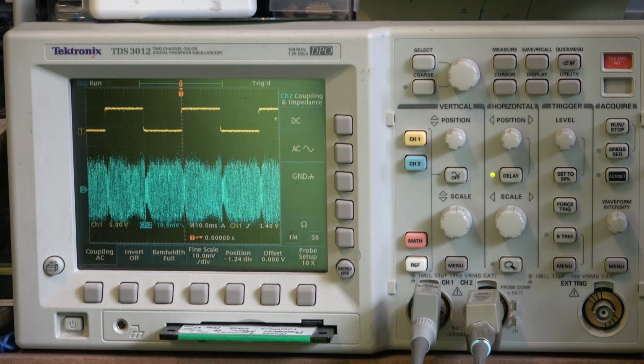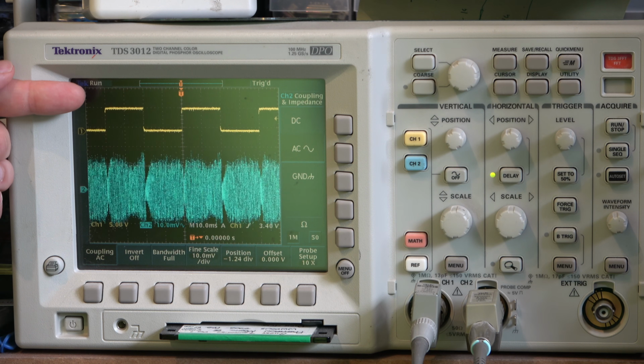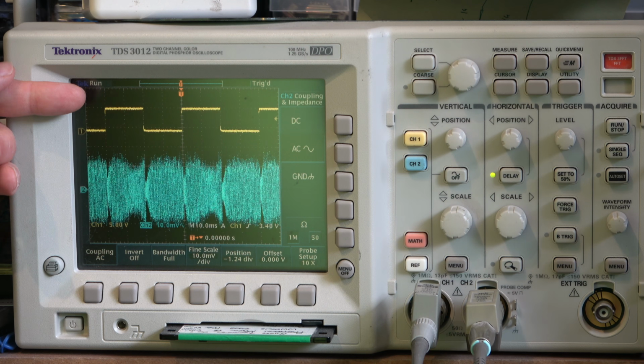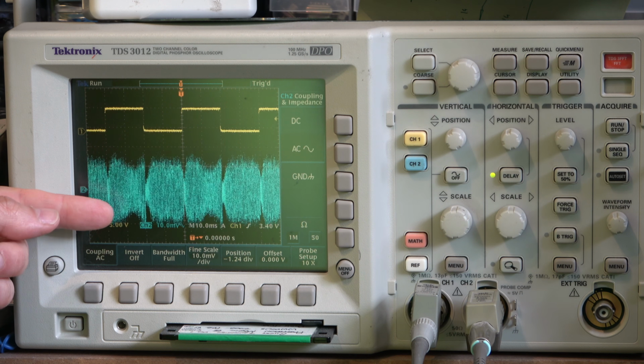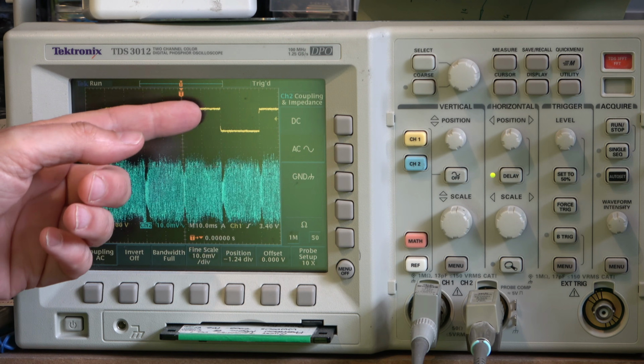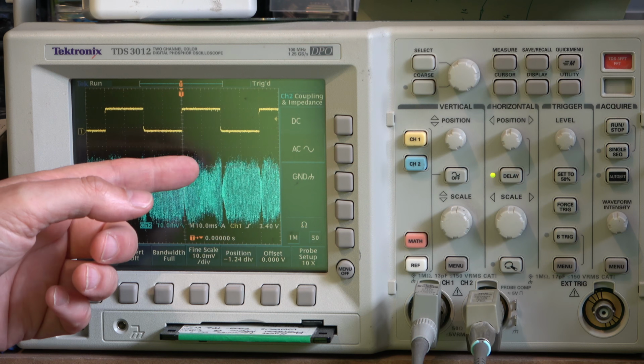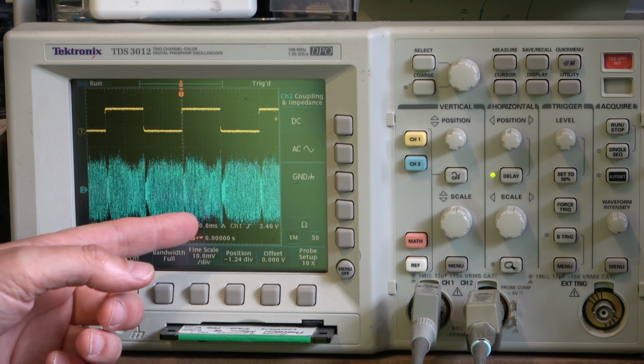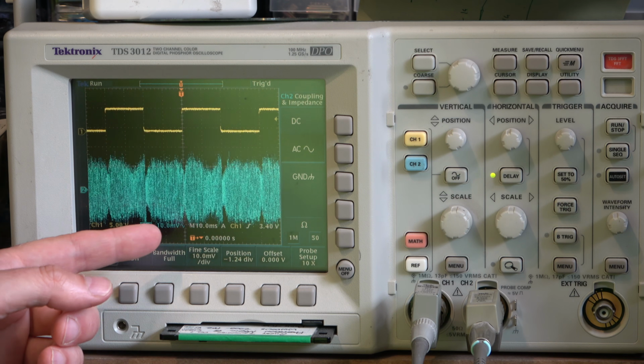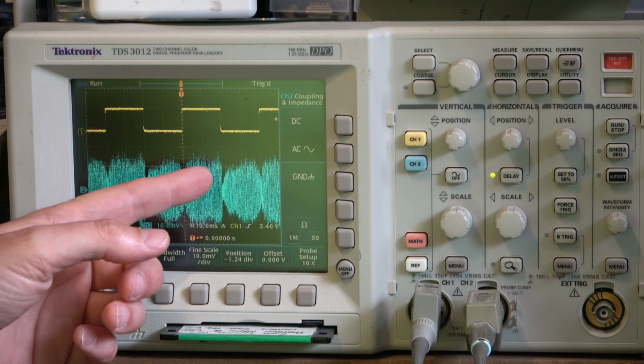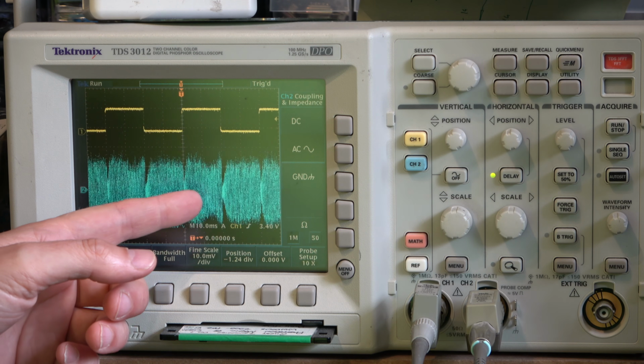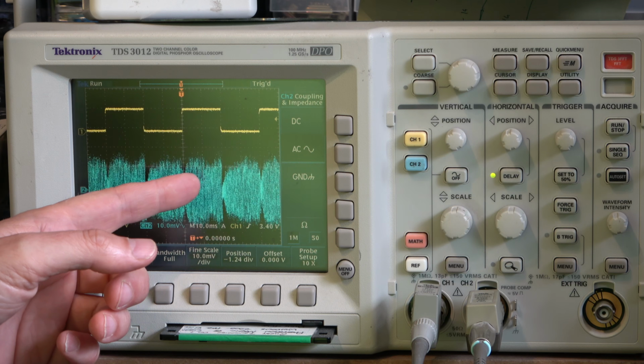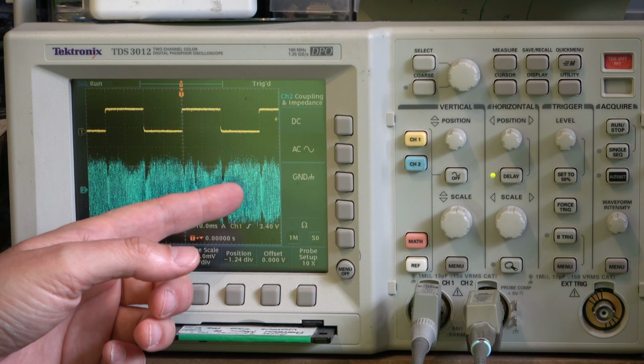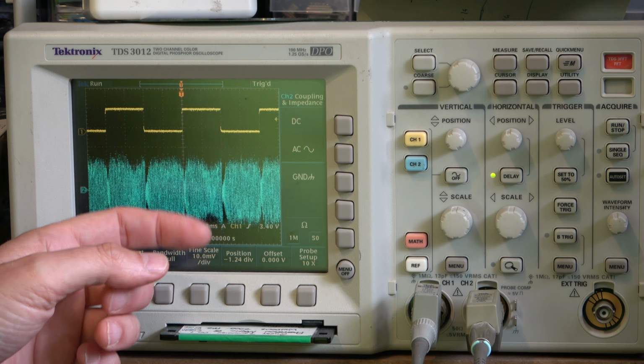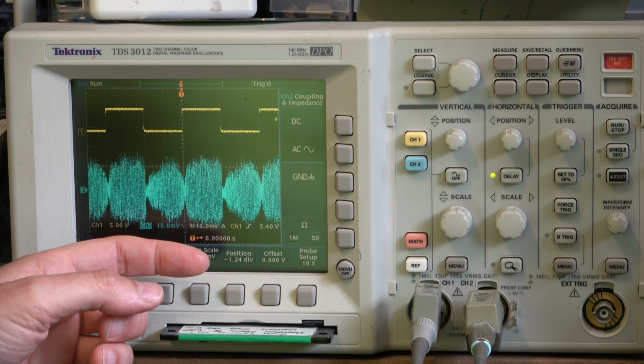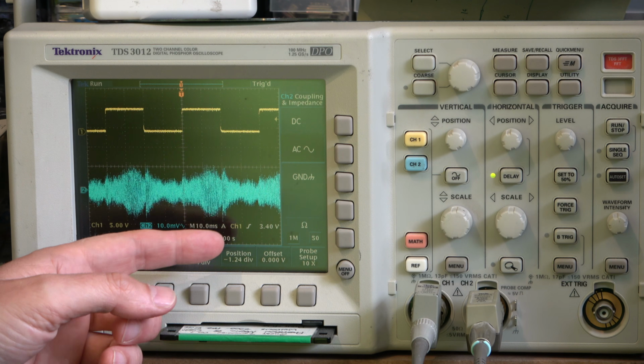So let me show you what we have here. The top trace is the head switching pulse. That tells us which head we're reading from. So the lower trace here is our RF envelope coming from the 2 heads. So that's one head and that's the other head. We've just got a repetitive waveform. The only information is what we're getting off these 2 heads. And if I adjust the tracking control on this machine, we will see the waveform slightly change. So we've got a full envelope on one head or a full envelope on the other, which implies there's something wrong with either the recording or the machine. It's not giving quite the results it should, but this is very much the sort of envelope you'd expect. And if I swing the tracking way off, then it just becomes a scrambled mess like that.